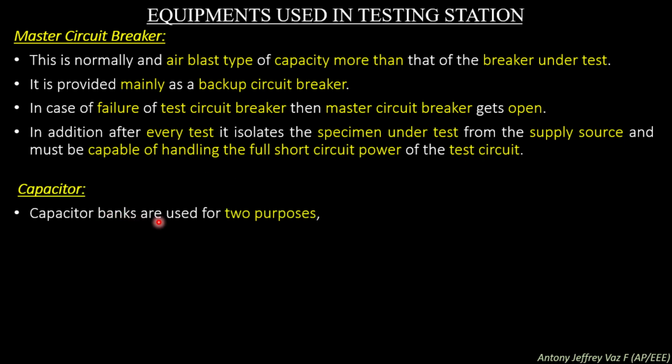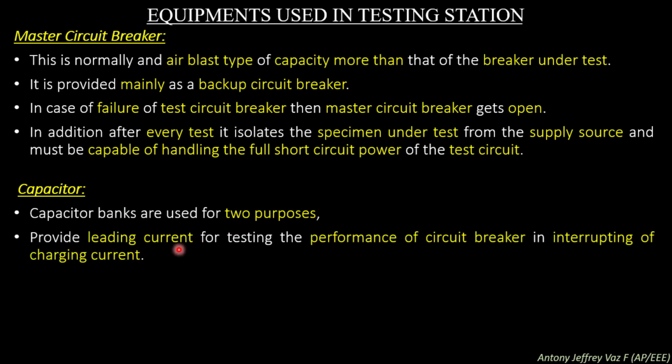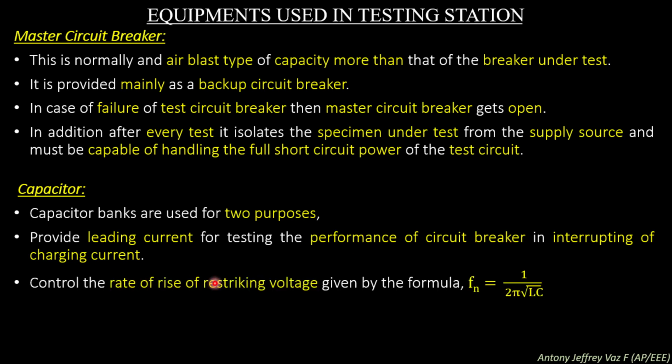Capacitor banks. Capacitor banks are used for two purposes. First, to provide leading current for testing the performance of the circuit breaker in interrupting charging currents. Second, to control the rate of rise of restriking voltage, given by the formula Fn equals 1 by 2 pi root of LC.